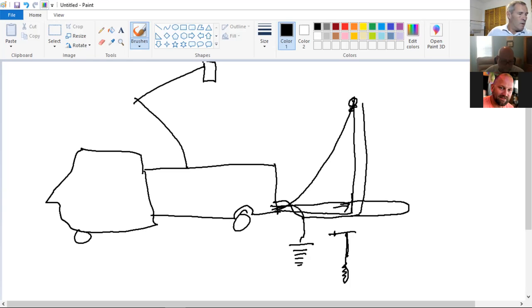What's the reason? It won't fail to ground, but if you have any kind of contact with the boom, this ground is rated pretty well. If you introduce the coil into it, it's going to intensify the voltage and the magnetic field. I've seen it happen once, where you blow the connector right off the ground rod because the contact intensified the voltage. If you had stretched it out and not created that magnetic field, since the coil intensifies both the voltage and the magnetic field, that wouldn't have happened.